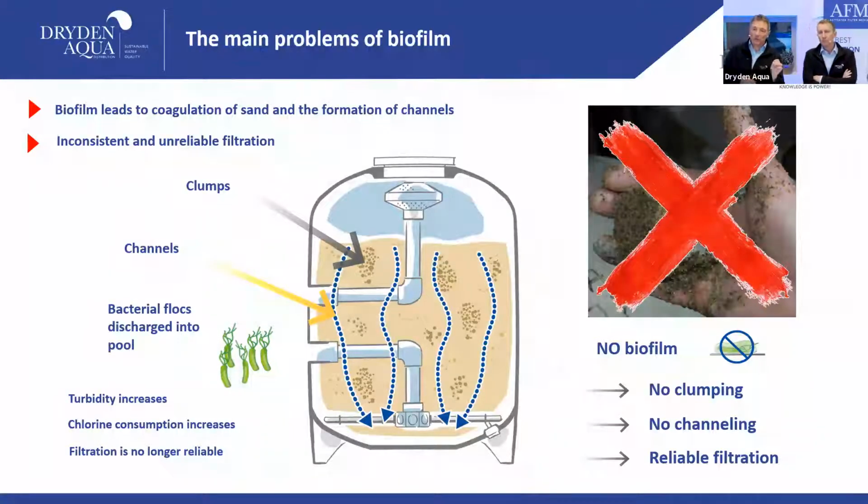And what's the problem with this bacterial flocs? Individual bacteria, planktonic bacteria, you easily kill them with a low chlorine concentration within a minute or half a minute. But when they are in flocs, they're not really sensitive anymore. Then it needs much longer.